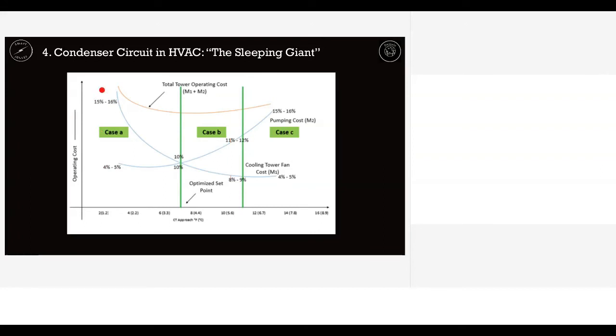So when the cooling tower approach increases, this axis is the cooling tower approach, and this is the cost in terms of energy cost. When the cooling tower approach is increasing, there's a sweet spot where the pumping of water in the condenser circuit and the cooling tower fan speed are matching. Both should be operated in the same condition. And on the right side of this graph, the condenser pump cost is increasing because the cooling tower is not effective and the cooling tower approach is high. So the condenser pump is actually doing more work in terms of heat transfer. So pumping is more, but fan speed is less.